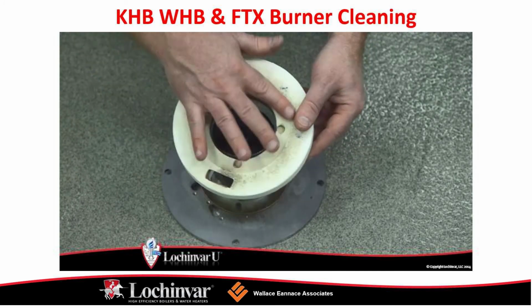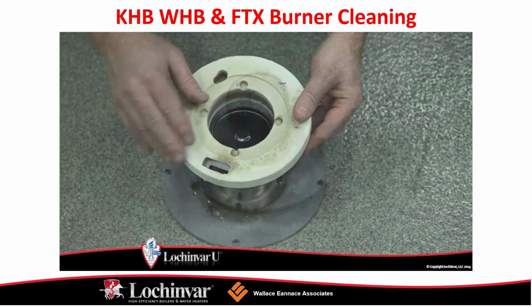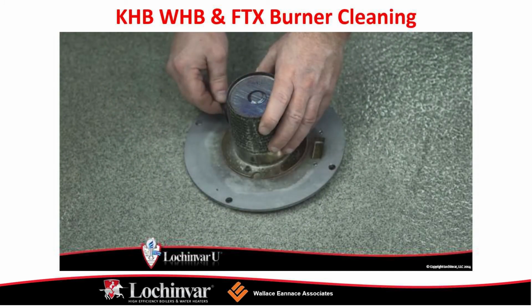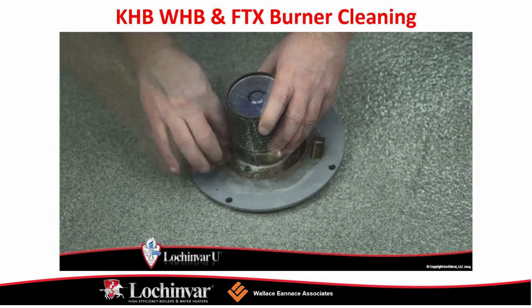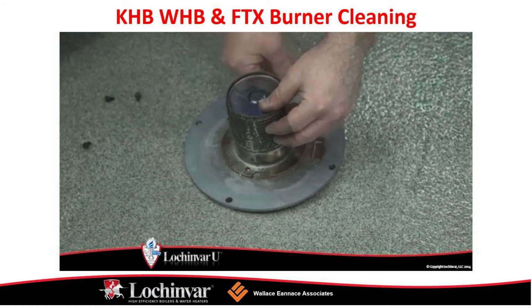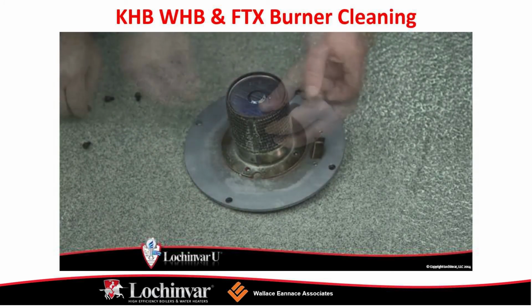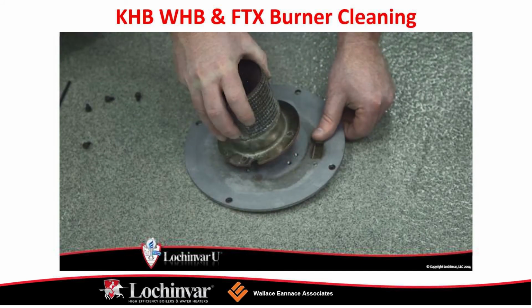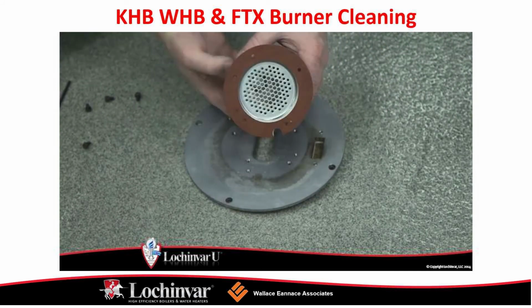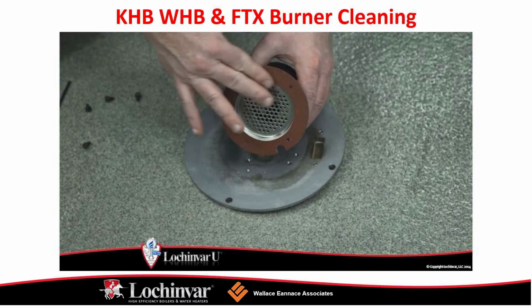A gasket is used to seal between the combustion air blower and the heat exchanger door. Care must be taken not to tear or damage the gasket or air shutter if equipped. If a gasket is damaged or torn, it must be replaced. Now remove the nuts securing the heat exchanger door to the heat exchanger.